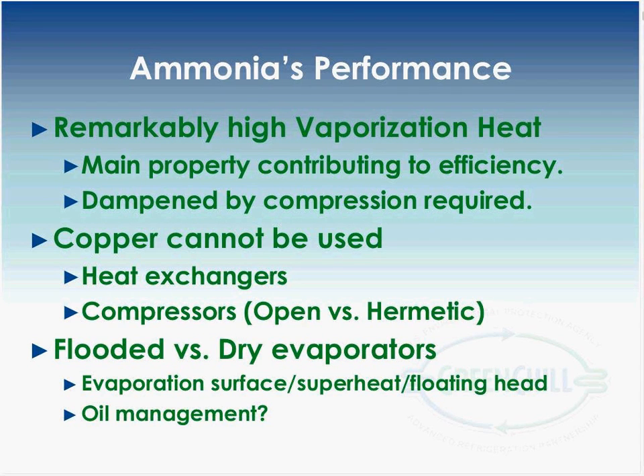I'll go into this later, but there is some recent compressor technology where they have used aluminum windings for a hermetic compressor, and it has been successful. There's a little bit of efficiency that you get with aluminum windings versus copper. I don't want to get into a huge tangent here, but flooded and dry expansion evaporators are both used with ammonia systems, and there are some efficiency factors that play into that. The flooded evaporator is probably the most typical evaporator you can see with ammonia systems today, even in smaller systems. It can get more efficiency out of the evaporator because every inch of the evaporator surface area is actually used to boil refrigerant instead of superheat it, and that gives you the low superheats back at the compressor, which makes that whole cycle more efficient.